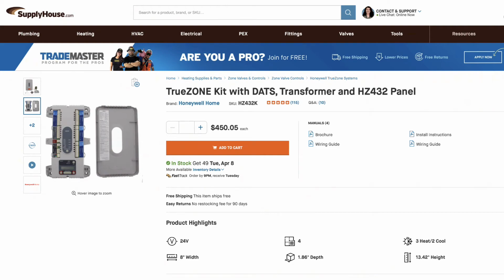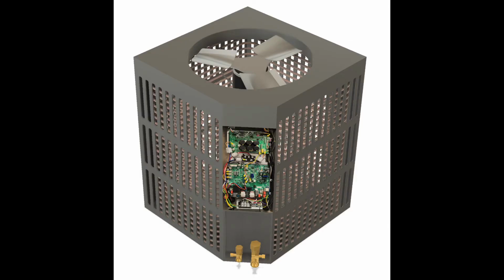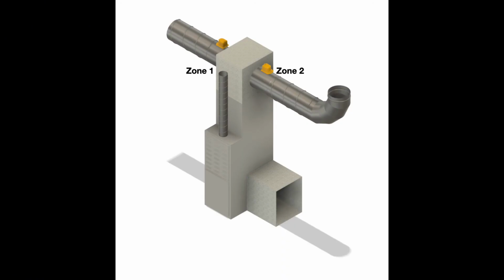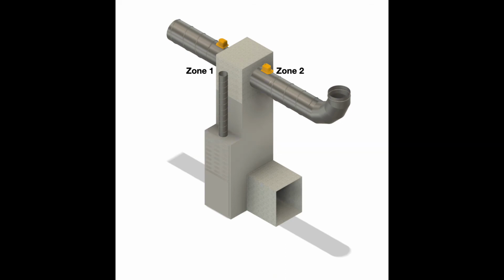And again, make sure you buy your control panel that can operate the number of zones you want and can operate the type of HVAC equipment that you have. For example, do you have a heat pump? Is it single stage or 2-stage heating and cooling? Or is it just single stage? Be sure to follow the installation instructions for whatever kit you buy. Some dampers are powered closed or powered open. Just make sure you understand the difference. Powered open means you need to supply 24 volts in order for the damper to open, for example. Also, you'll usually need a thermostat in each zone that will talk to the controller.